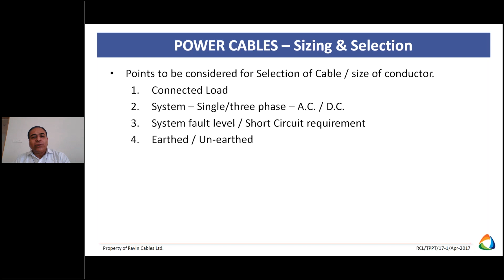What is the voltage system? Since power is the product of voltage and current, what is your voltage level? Then what are the other factors? We can say environment conditions. How are cables laid? Whether cables are laid in the ground or air, because current rating depends on these conditions. Basically, current rating is directly proportional to delta temperature. Delta temperature means the temperature at the conductor side minus the temperature in the environment. That is the delta.